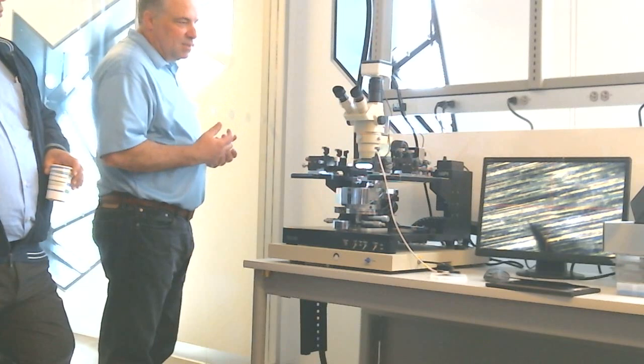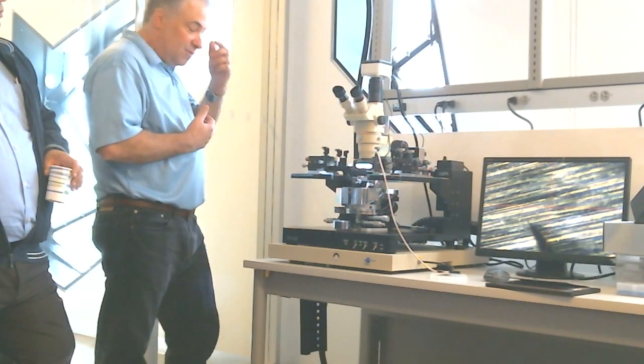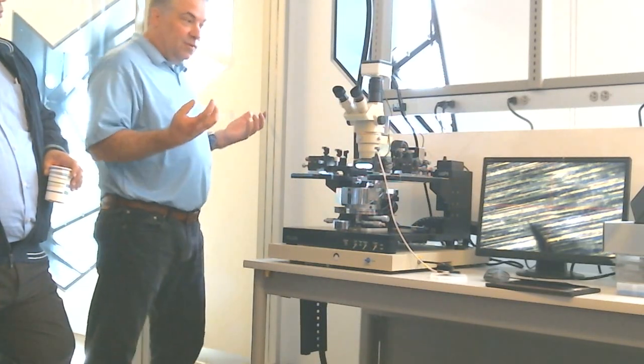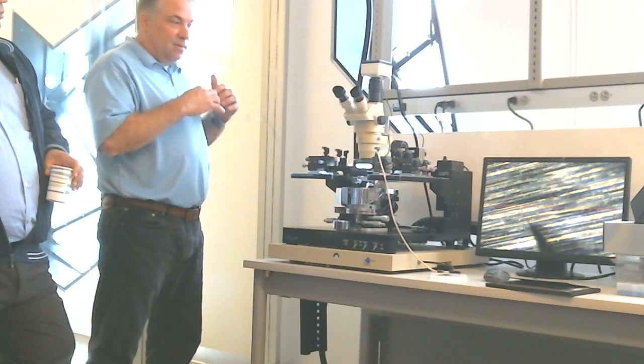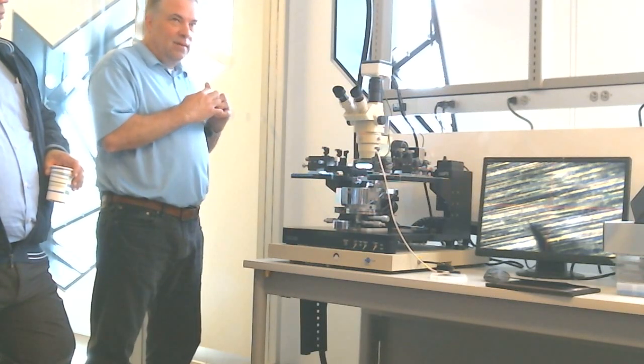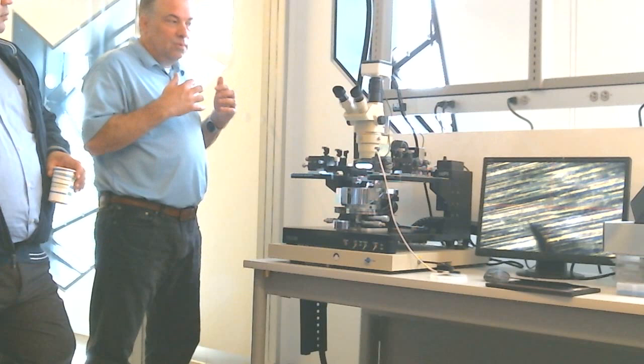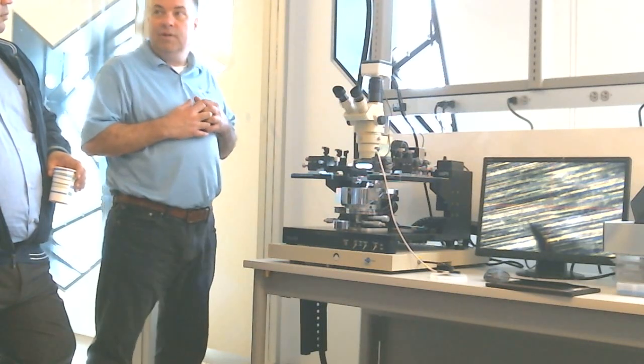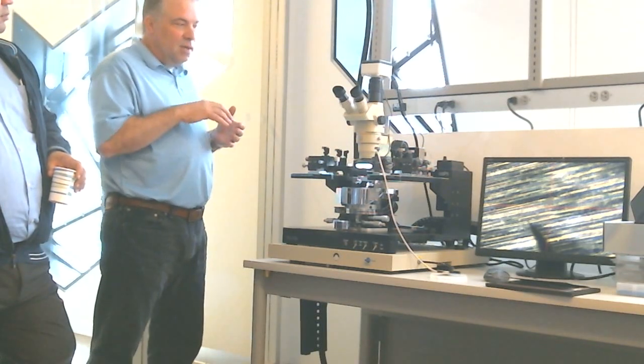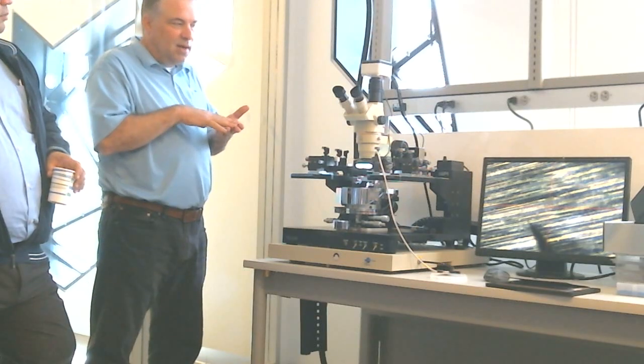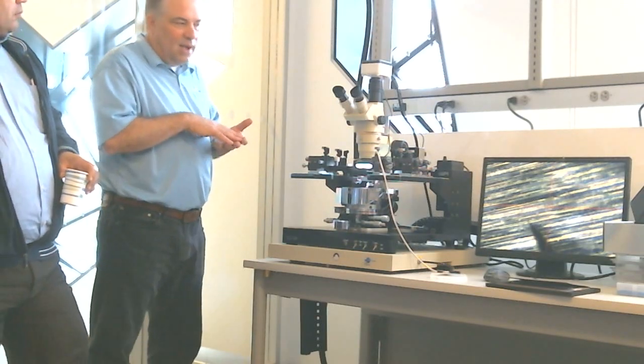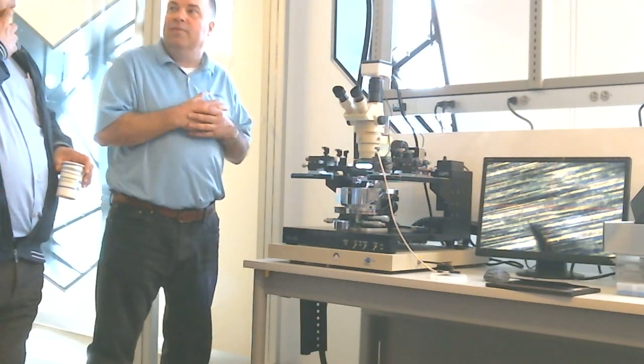What I see some customers do is for their particular test, they'll turn on their measurement equipment and they'll just slowly bring them down until they get a good measurement, and then they know that they have enough scrub. They know when they have enough probe pressure on there. If you just touch them, sometimes you don't make a good contact, it needs a little bit more. How much, it really depends on the device, the pad, the probe.